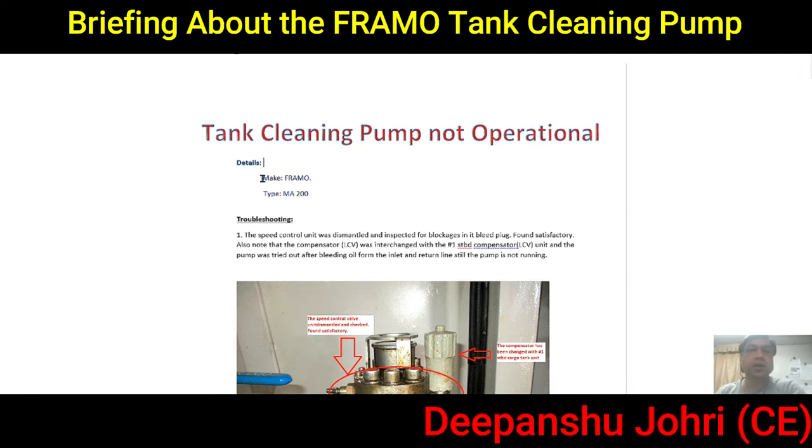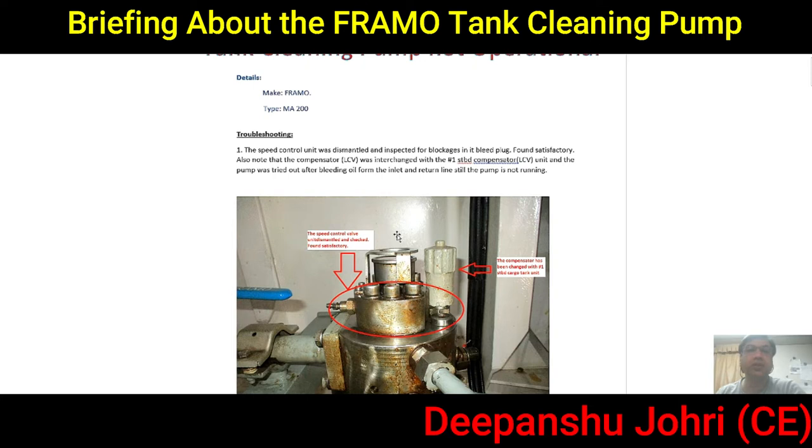This is a FRAMO type pump — the make is FRAMO and the type is MA200. The troubleshooting we carried out included dismantling the speed control unit for inspection of blockage, checking the bleed plug which was found satisfactory, and also interchanging the local control valve with the one from the starboard compensator unit. The pump was then tried out after bleeding the oil.